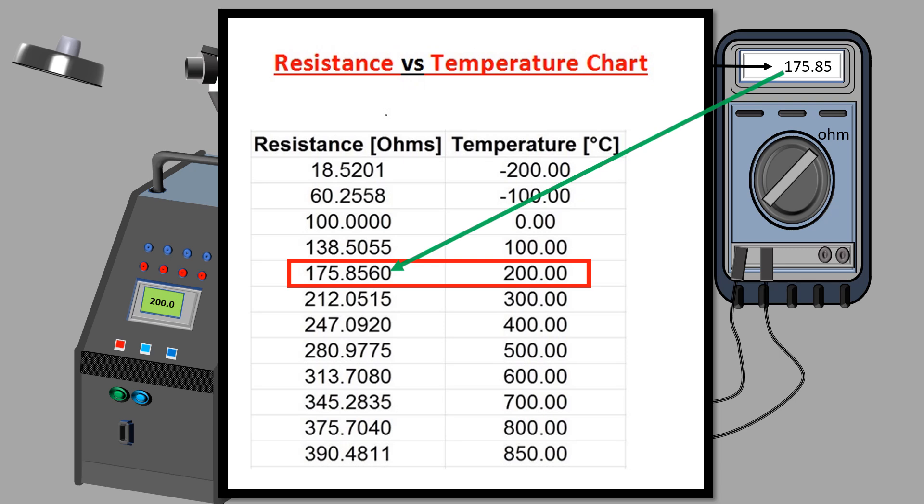The user now makes a record by entering this value of temperature detected by the RTD and the temperature displayed on the calibrator. This procedure is repeated for a few other set of temperatures within the range for which the RTD is used and the readings are recorded.